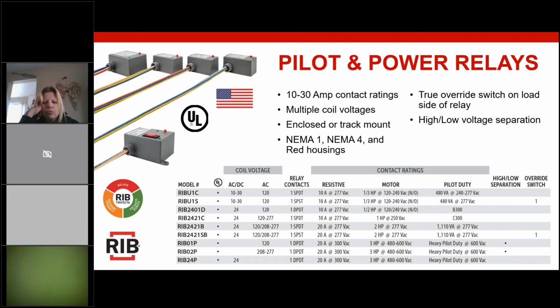We do have a true override switch, which is located on the load side of the relay, so you can override. And then we have optional T-style versions of relays that have a true high-low voltage separation with some fish paper. We know that there are some areas of the country where the electrical inspectors are a little bit more stringent on those requirements, so we have those in our offering.